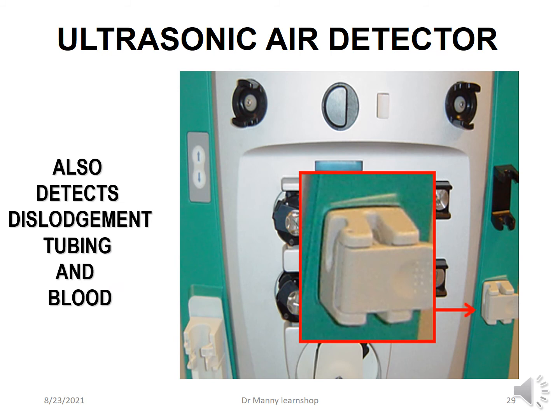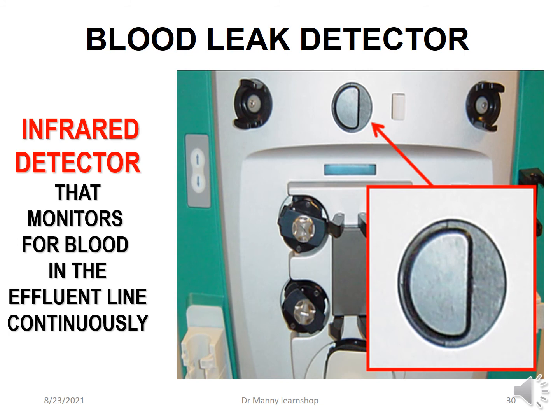Now, the ultrasonic air detector detects air just before blood returns to the patient. Therefore, this prevents catastrophic situations which could result in an air embolism. But it also detects dislodgement of the tubing and blood in the line, even though it's not the blood leak detector. So if the tubing isn't in the correct place, it will alarm and alert because it's detecting air. The blood leak detector is an infrared detector that monitors for blood in the effluent line continuously. Any blood detected, it will alert.